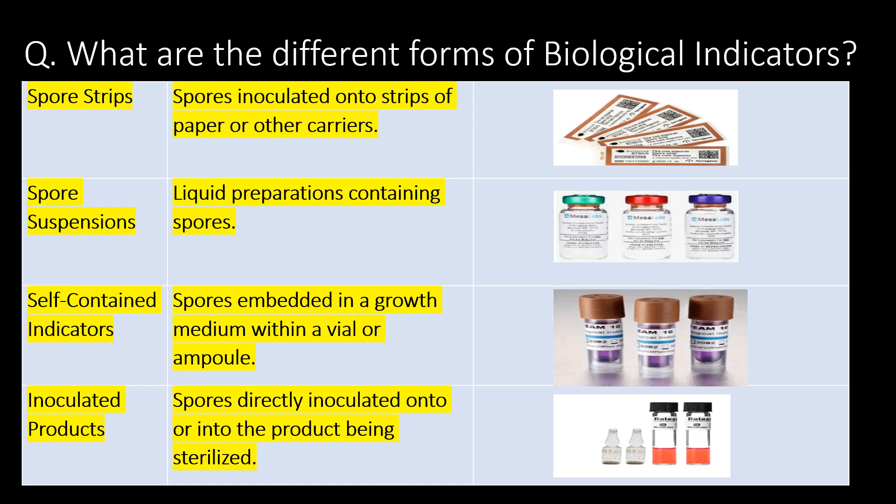What are the different forms of biological indicators? First, spore strips — spores inoculated onto strips of paper or other carrier. Second, spore suspensions — liquid preparations containing spores. Third, self-contained indicators — spores embedded in a growth medium within a vial or ampoule. Fourth, and very importantly, inoculated products — spores directly inoculated onto or into the product being sterilized.